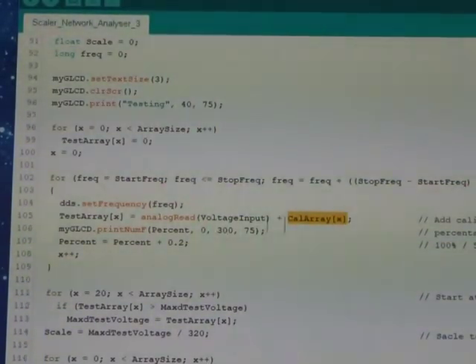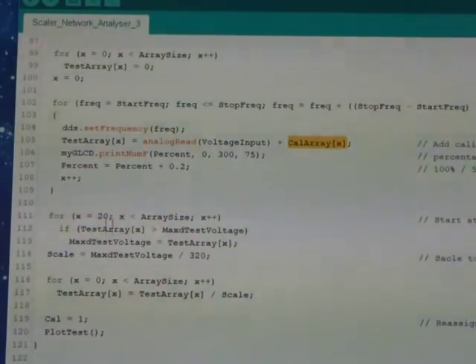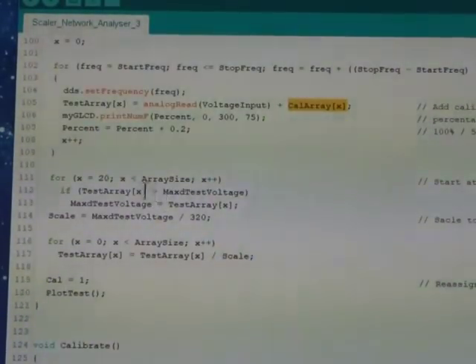So now we're basically taking into consideration any inaccuracies or non-linearities we have with the test setup. And of course then it also tells you by your percentage complete. Once it's completed doing that, we need to do a bit of scaling to make sure that 0 dB, or the maximum or least amount of attenuation, is at the top of the screen.